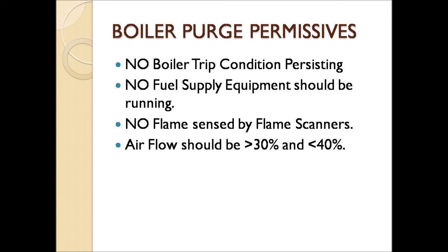In a power plant, for each and every operation there are certain permissives. Likewise, boiler purge also has some permissives. For ease of operation, we have divided these permissives into 4 major parts. The first is no boiler trip condition should be persisting. The second is no fuel supply equipment should be running. The third is no flame should be sensed by any flame scanner in the boiler furnace. The fourth is air flow should be greater than 30% and less than 40%.